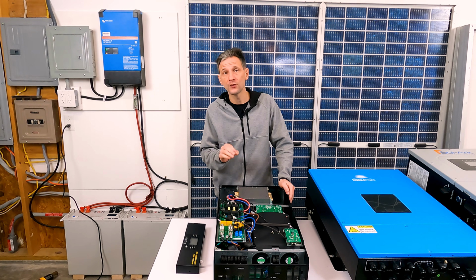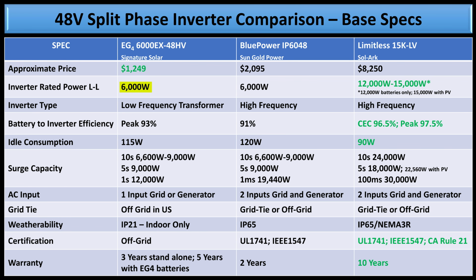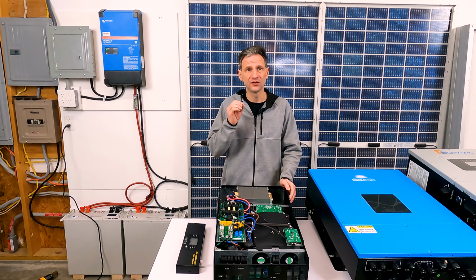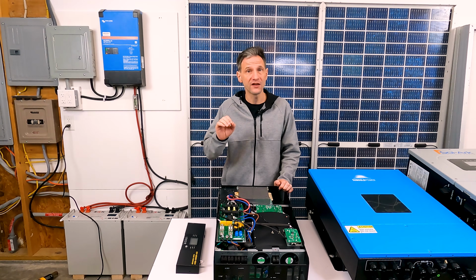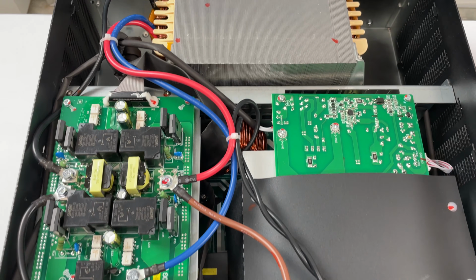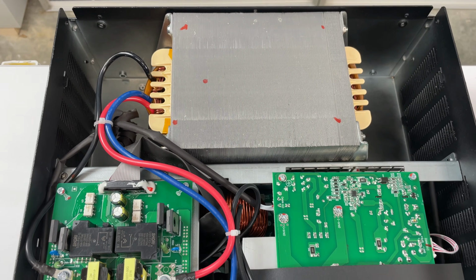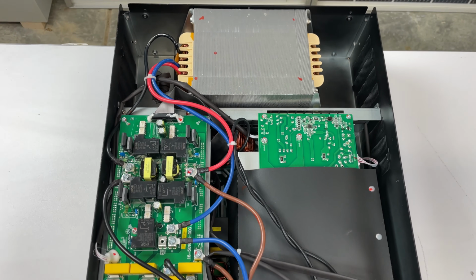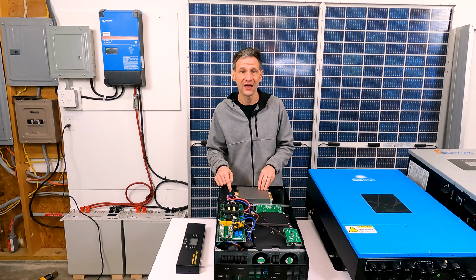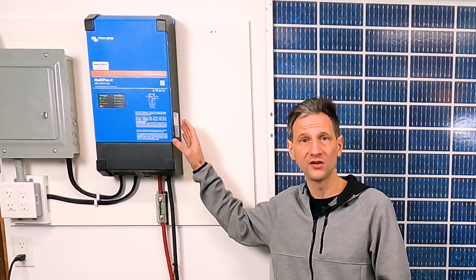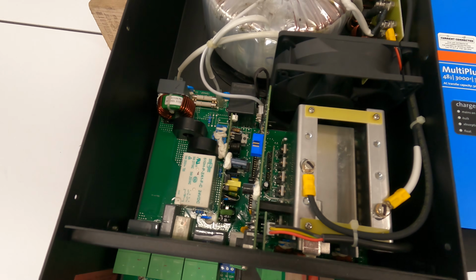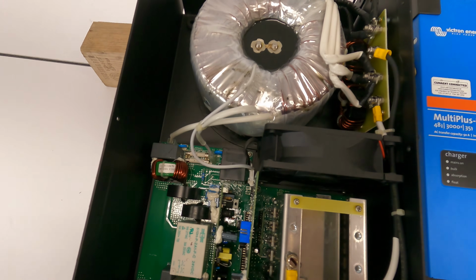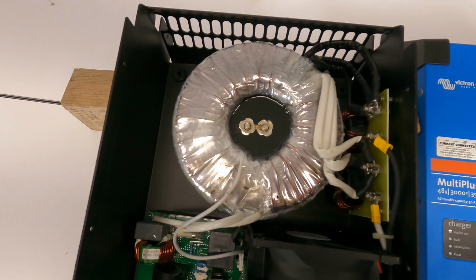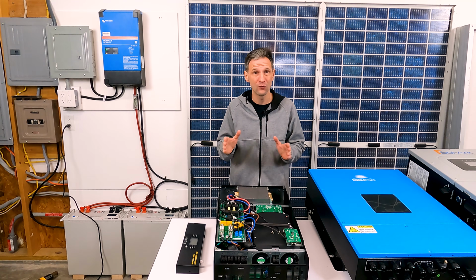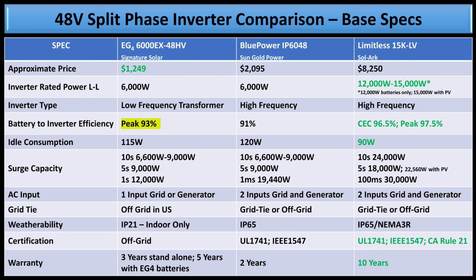It's rated for 6,000 watts, which is 3,000 watts per phase. But because it's a low-frequency inverter, it's great for starting heavy induction loads like well pumps and air compressors. You can identify it as a low-frequency inverter by this giant square transformer, which has a center tap for the 120 volt output. The more expensive Victron that we installed a few weeks ago has a more efficient toroidal transformer. However, even with this low-cost square transformer in this unit, it still does very well with a 93% peak efficiency.